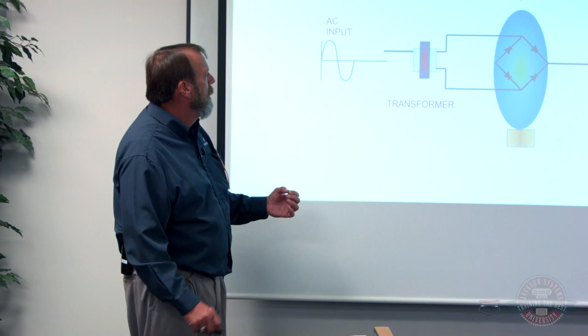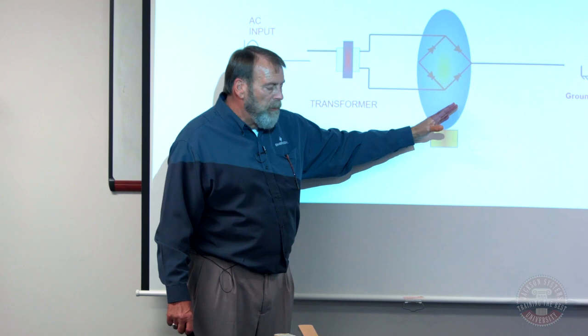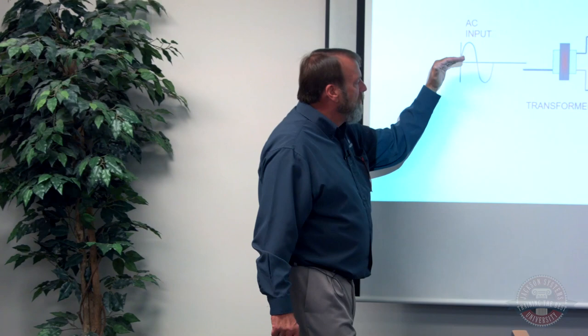So in rectification, that's exactly what we do. We pulse one way, we inhibit coming back the other way. As long as the flame's present, we can do that. No flame present, we've got a real problem, no electrons flow. So here you see where you have your alternating current, but because it's rectifying, I just get a DC input.